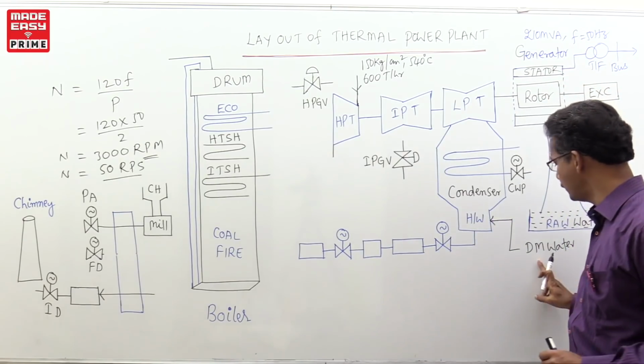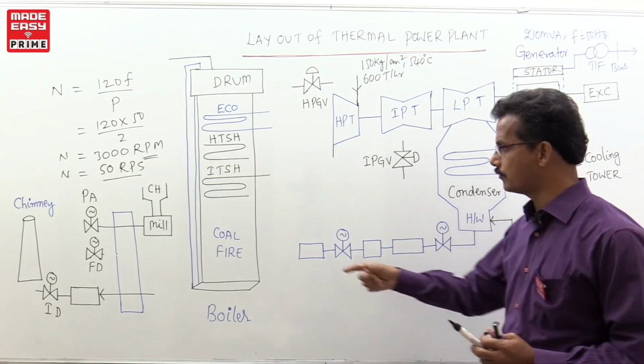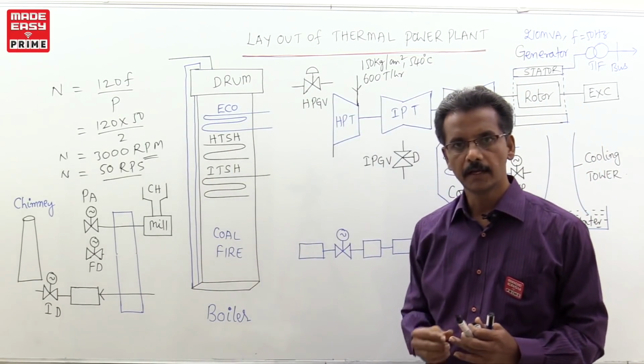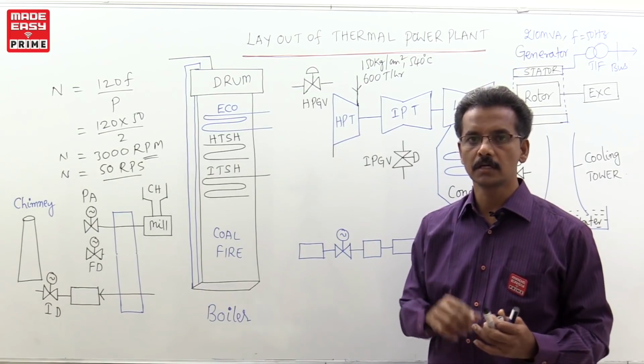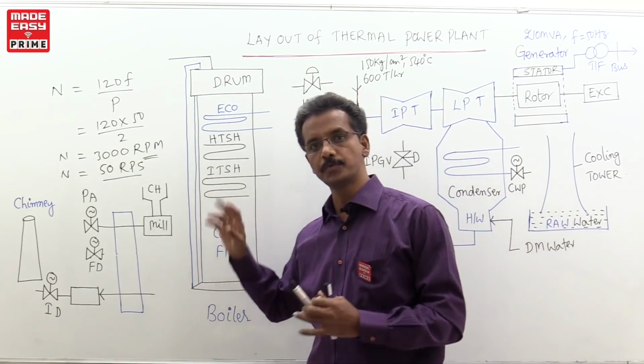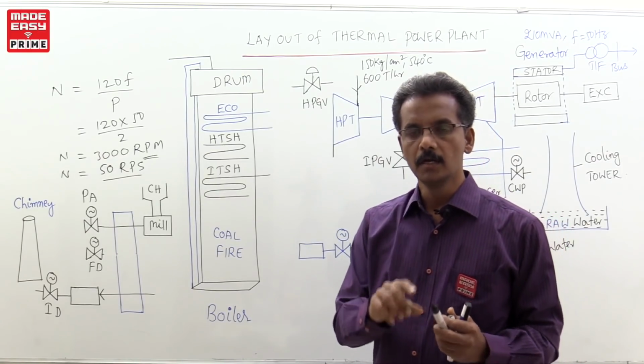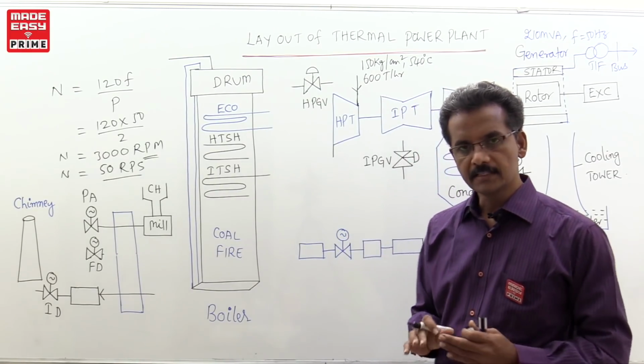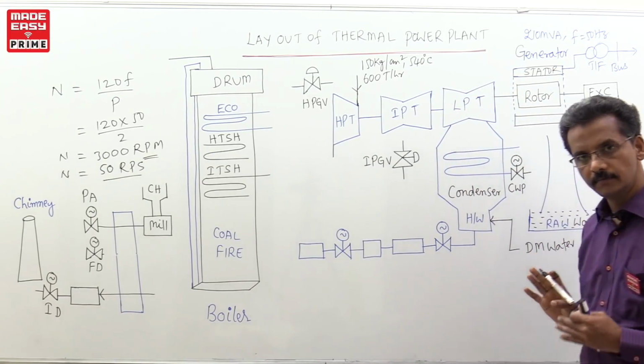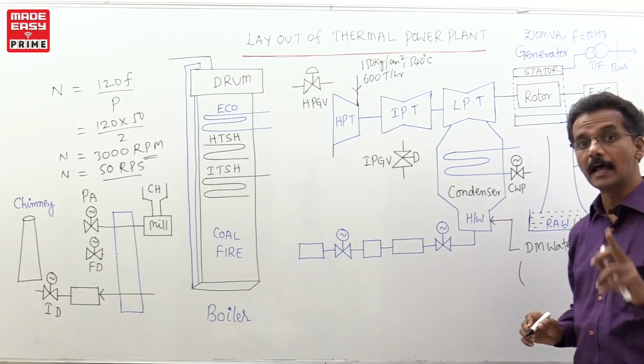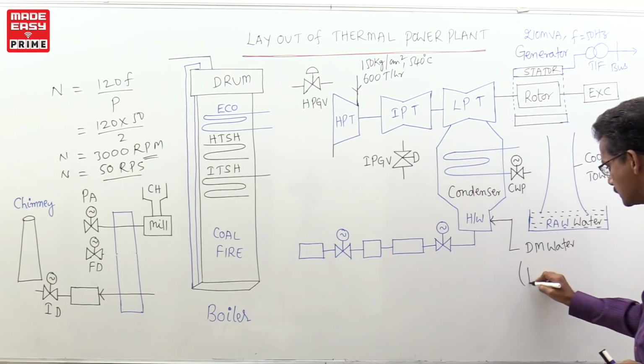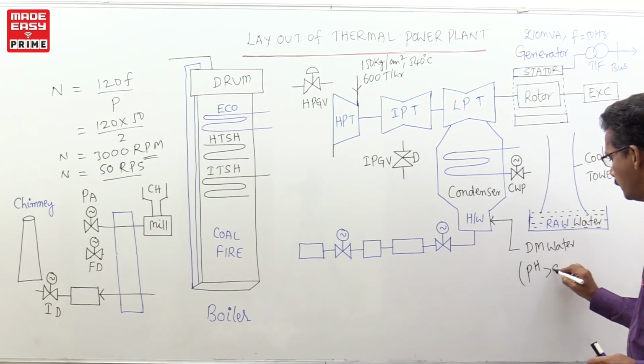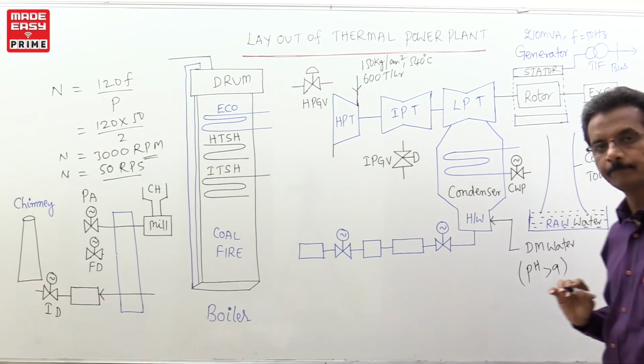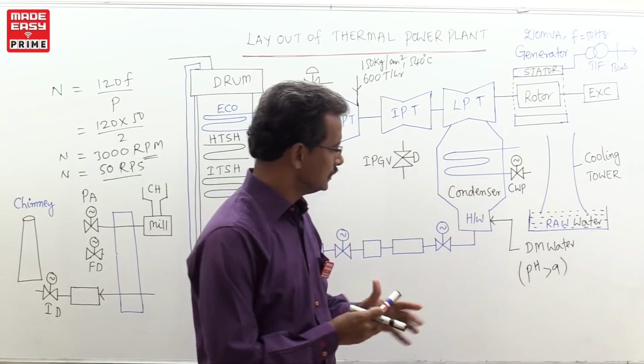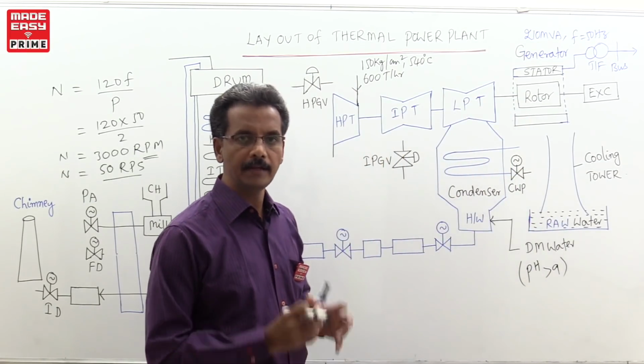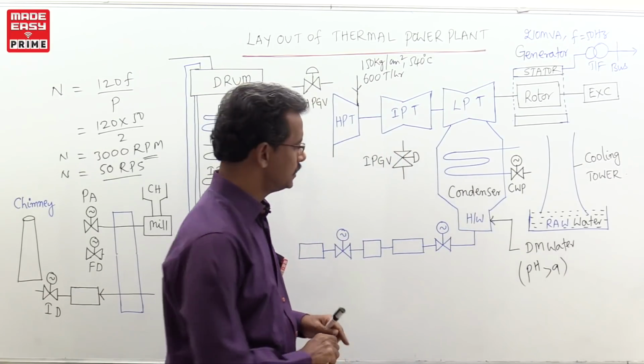What is the need of making DM water? If mineralized water is sent through the boiler tubes, then scaling will form, which will cause corrosion and the boiler tubes will get damaged. Because of that, we completely remove the minerals inside the water and use DM water. This DM water should not be acidic; it should be alkaline. For that purpose, the pH value of this DM water is maintained at more than 9, around 10. So DM water with pH more than 9 is filled inside this hot well.